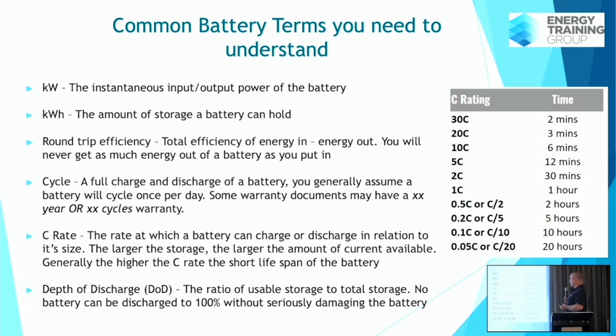Finally, depth of discharge. A battery cannot discharge to 100%. If you discharge a battery entirely, the battery is cooked, it's a brick, you're going to throw it in the bin. Most lithium batteries will have a depth of discharge of around 90 to 95%. That's why lithium batteries are so much smaller than lead-acid storage systems, because the old school lead-acid systems had a depth of discharge of around 50% if you expected the battery to last longer than 3 or 4 years. So there was an awful lot of battery that used to get left on the table.